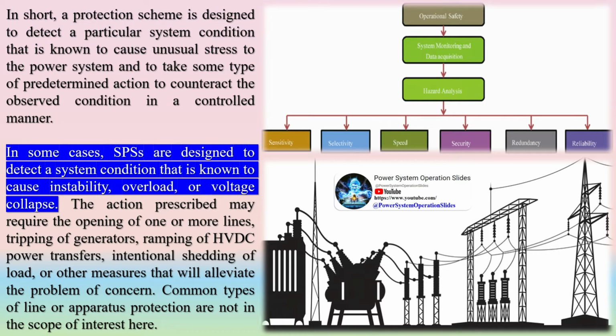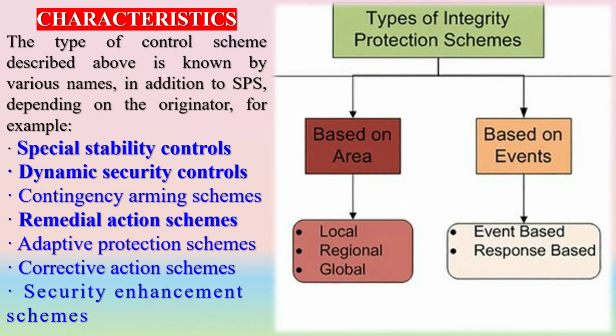In certain power systems, studies of system performance may show that large disturbances on important lines or facilities can cause violent and often disastrous effects. This may occur in systems that are interconnected by long or weak tie lines, which may be heavily loaded. When this occurs, the system may break apart in a way that is not predictable, and with the possible creation of power system islands having large generation to load imbalances. These poorly balanced islands may not be able to survive, resulting in a total blackout.